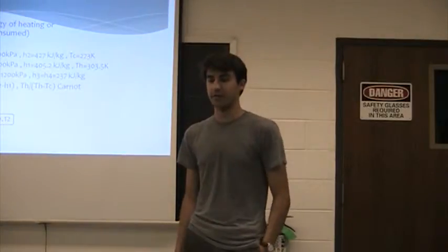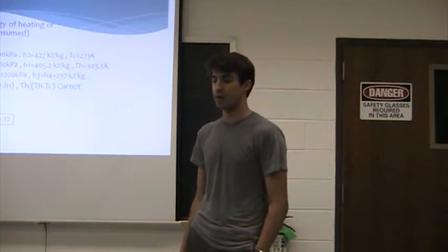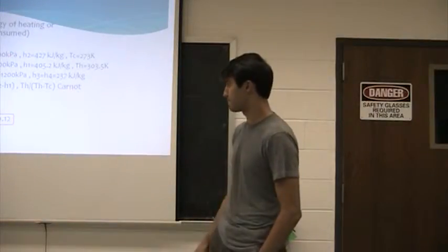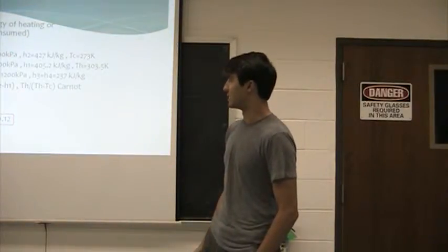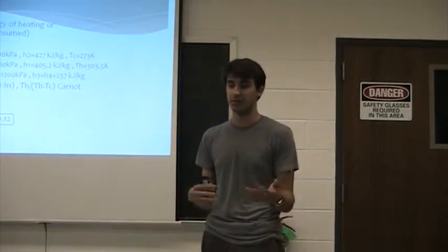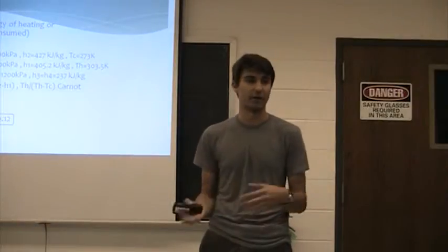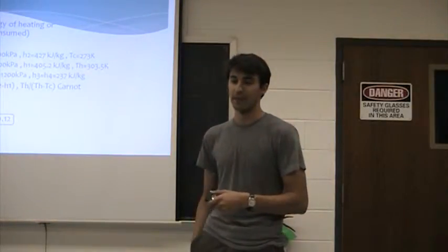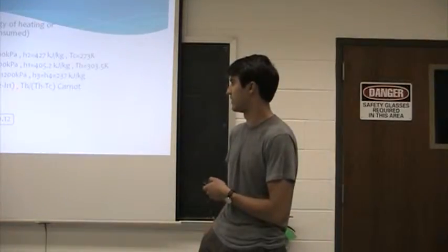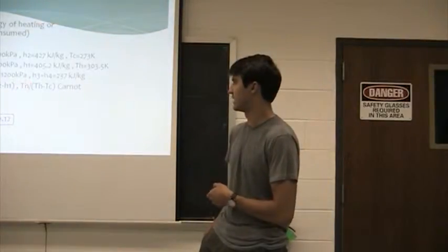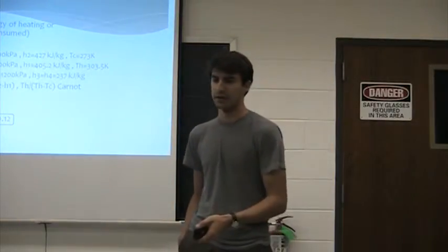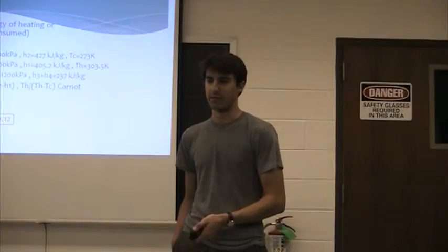So I ran a few numbers. We assume that our evaporator will be at 500 kPa, our condenser will be at 1200 kPa. And to calculate the COP, you take the energy it takes to heat or cool, and divide it by the power consumed by the system. I got something similar to Thomas, 7.7 for our COP. Then I ran a Carnot equation and found it to be 10.12. I found this in the thermodynamics book, and I decided to just do that math.